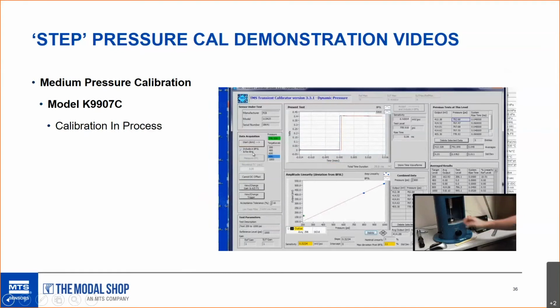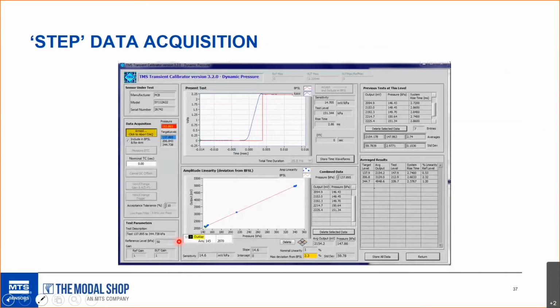See there, he slides that mass down the valve stem, and he collects data over and over again like before. The other thing you'll notice is in the time domain data up here, the step rise data, it's a lot faster. That's just not scaling. This unit has a rise time of like 30 to 50 microseconds compared to the millisecond durations that are in the 903. But very similar process. And then the data acquisition slows down a little.